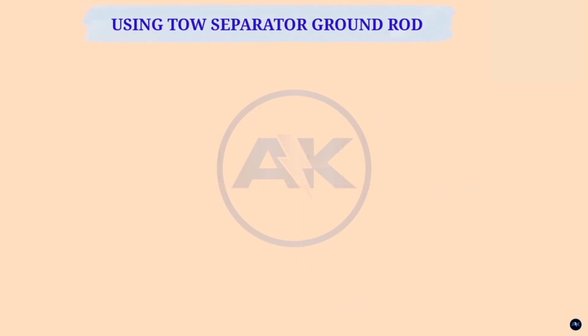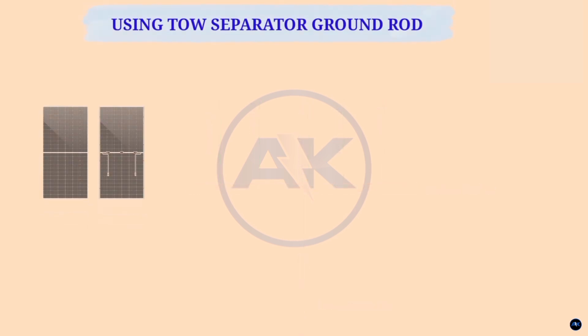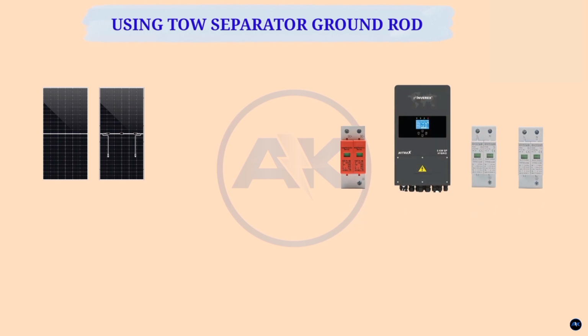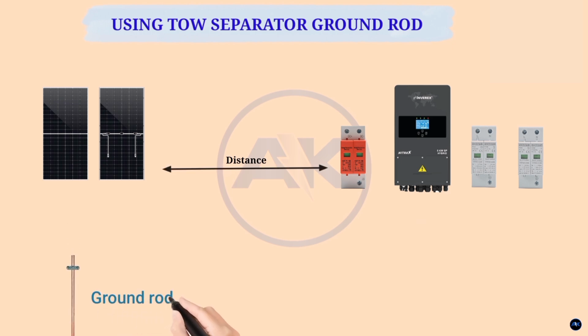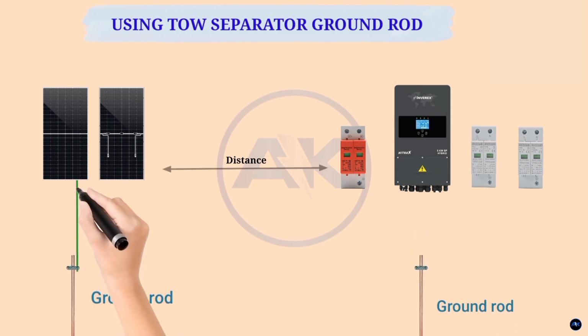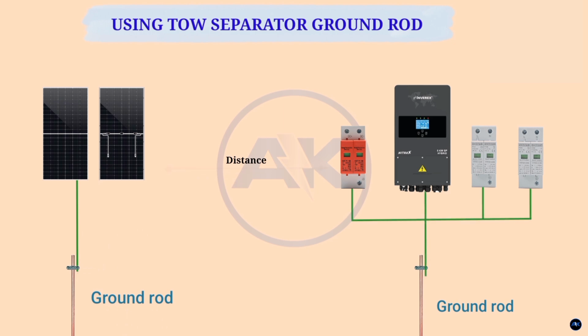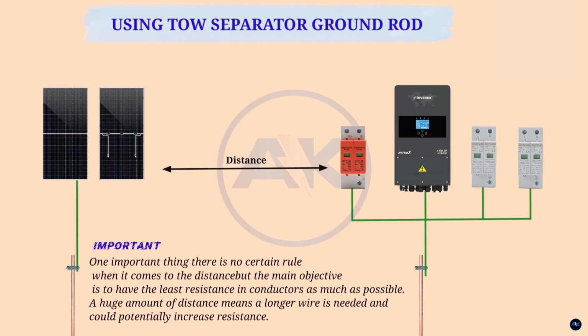Now let's take a look at using two separate ground rods. We have our PV array on this side and the main system on this side. If there is a huge distance between these two, it's better to have a ground rod for your PV array and another one for the main system. Connect your PV array to the first ground rod and the main system to the second. One important thing: there is no certain rule when it comes to the distance, but the main objective is to have the least resistance in conductors as much as possible. A huge distance means a longer wire is needed and could potentially increase resistance.